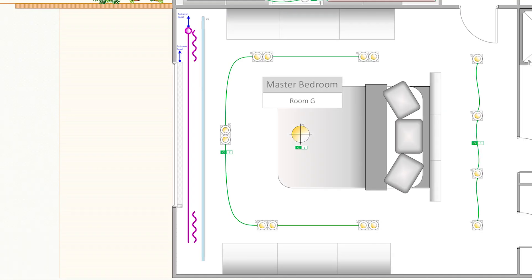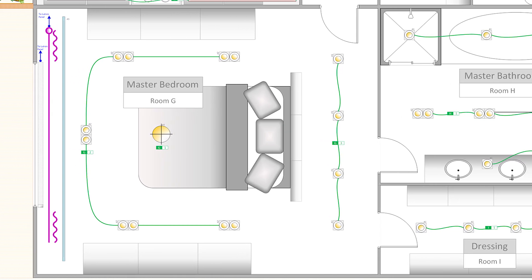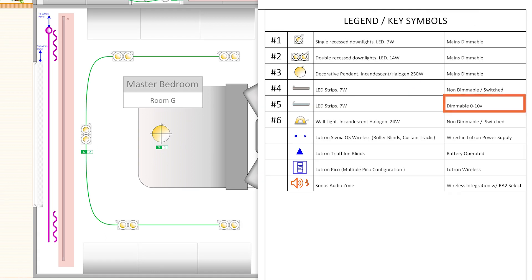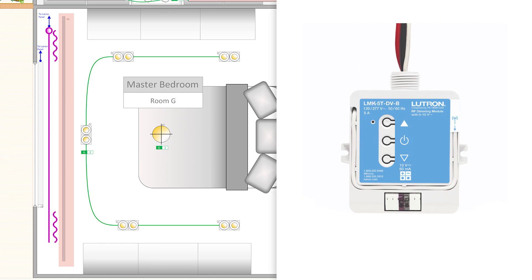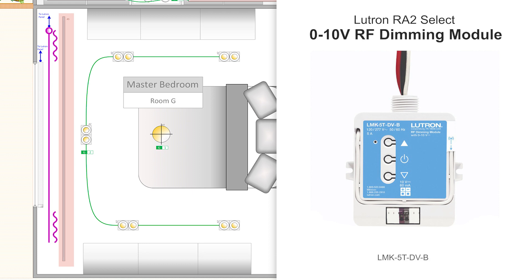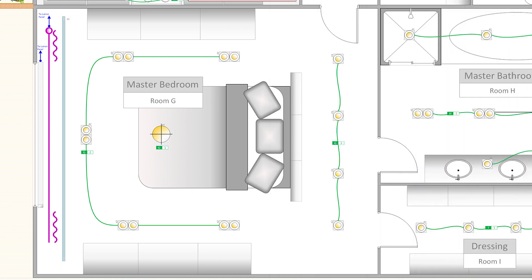While we are in the master bedroom, let's talk about another kind of load type we can use on the RA2 Select system. Here I have another type of LED strip, and when I check back on the legend, it says it is a 0-10V dimming circuit. To operate a 0-10V lighting circuit on a RA2 Select application, we need to use the 0-10V RF dimming module. 0-10V lighting circuits require an additional pair of cables to carry the dimming signal, and the regular inline dimmer hasn't got this feature, so we have to use the 0-10V RF dimming module in this case.